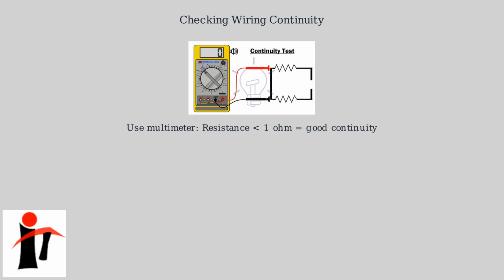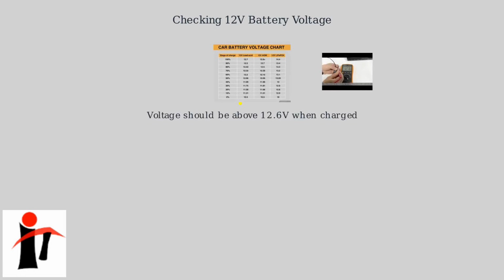To troubleshoot, use a multimeter to check wiring continuity. Set to continuity mode and test resistance. It should be less than 1 ohm for good connections. Next, check your 12-volt battery voltage using the multimeter. A healthy battery should read above 12.6 volts when fully charged.